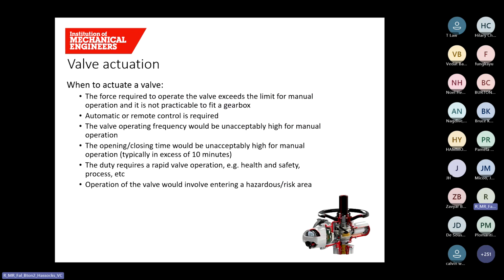Let's consider when to actuate a valve. When manual operation is impractical due to high torque requirements and fitting a gearbox is not feasible. The system demands automatic or remote operation for efficiency, safety, or integration with control systems. The valve is operated so frequently that manual control becomes inefficient or unsustainable.